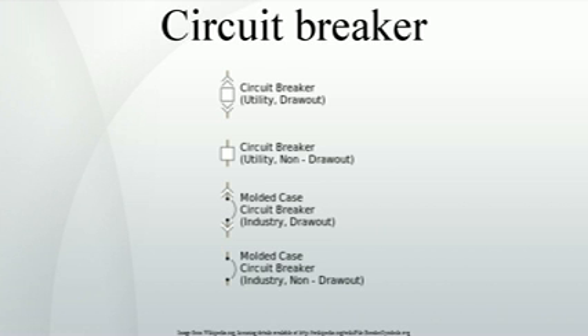Disconnecting circuit breaker, DCB. The disconnecting circuit breaker, DCB, was introduced in 2000 and is a high-voltage circuit breaker modeled after the SF6 breaker. It presents a technical solution where the disconnecting function is integrated in the breaking chamber, eliminating the need for separate disconnectors. This increases the availability, since open-air disconnecting switch main contacts need maintenance every 2 to 6 years, while modern circuit breakers have maintenance intervals of 15 years.